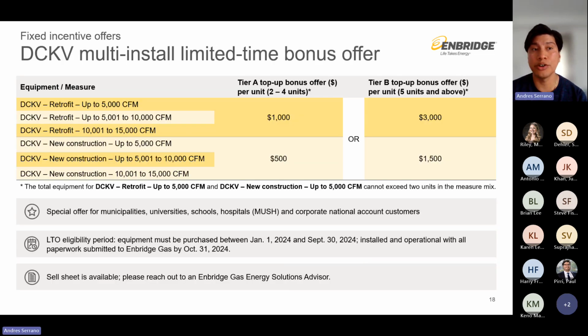And the last special offer under our fixed incentive is the DCKV multi-install limited time bonus offer. Just to give you a bit of background on what a DCKV is, we typically see exhaust fans in commercial kitchens operating on an on-off basis. The air that is being exhausted typically is replaced with fresh and heated air during the winter months. This is seen as a huge waste of energy, especially when the exhaust fan is on while no one is really cooking. So a DCKV will detect cooking byproducts and send the information to a DCKV processor to adjust the exhaust flow accordingly, reducing the amount of fresh air that is heated and the amount of fresh air that is wasted when the exhaust fan is just running.